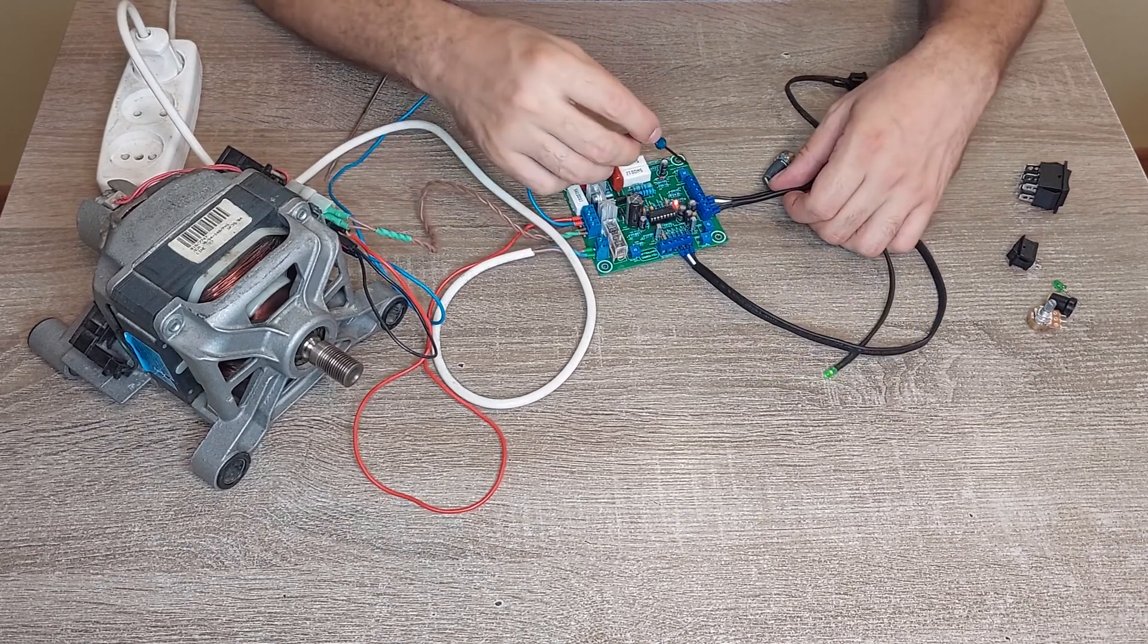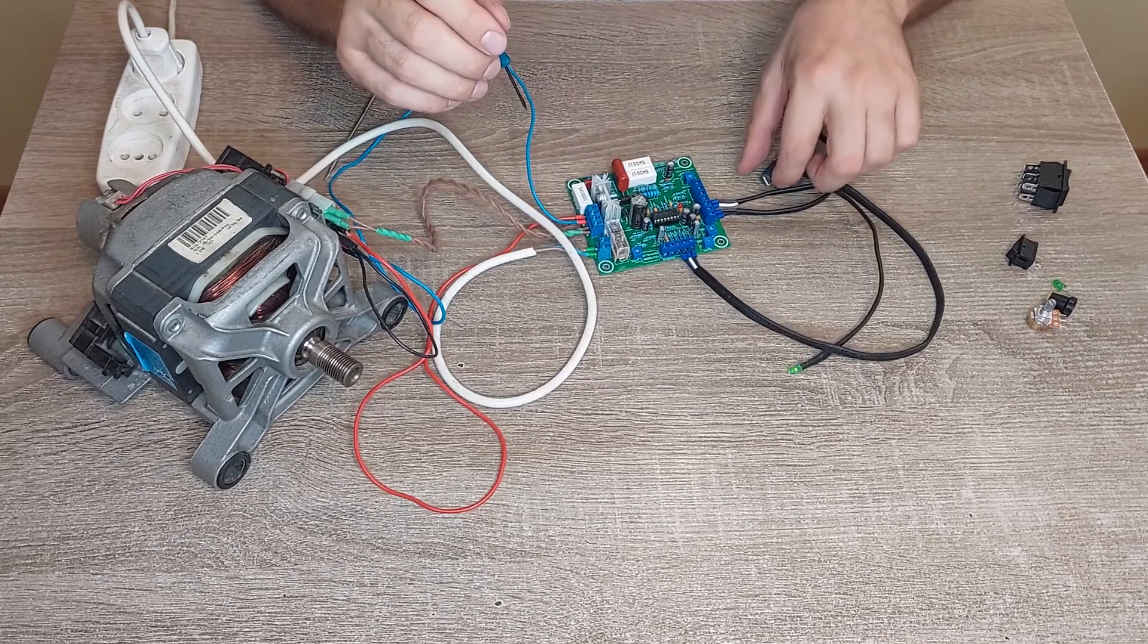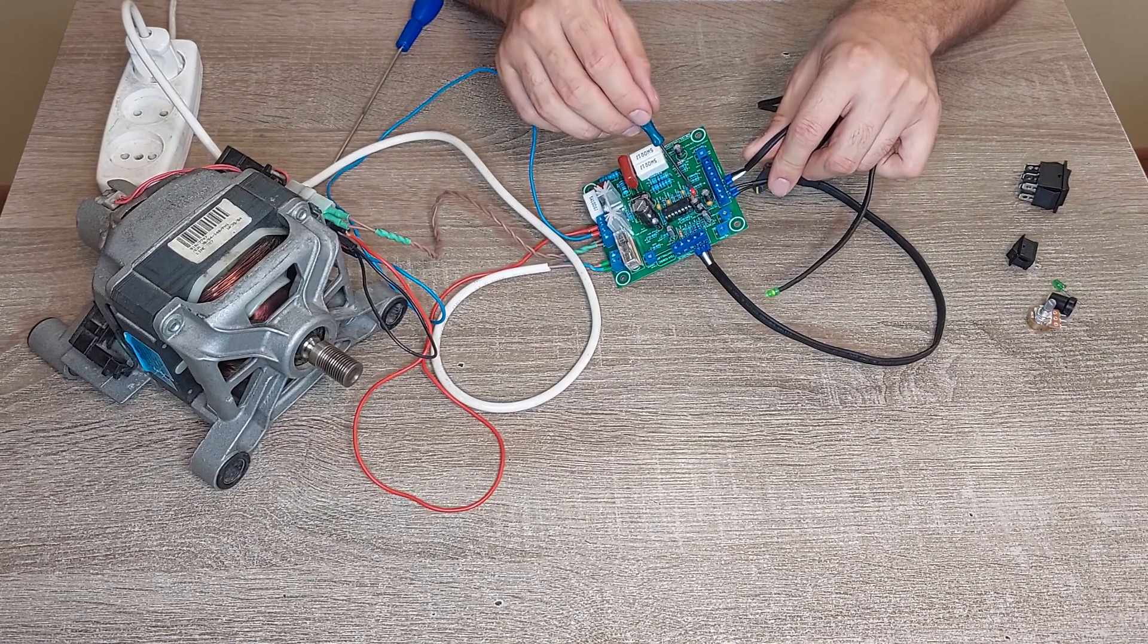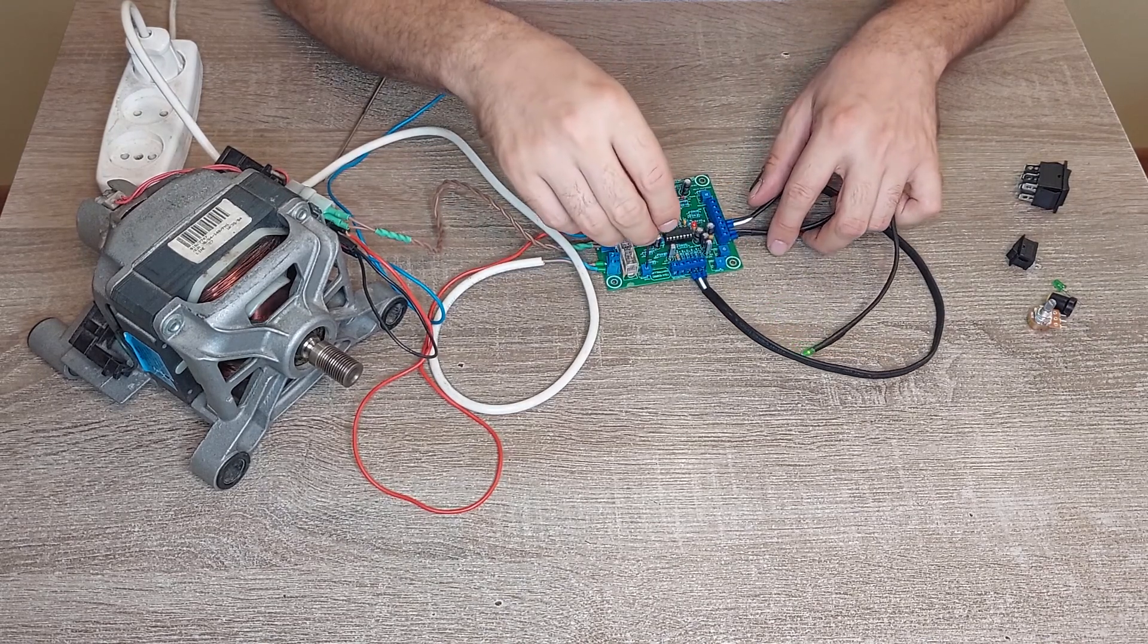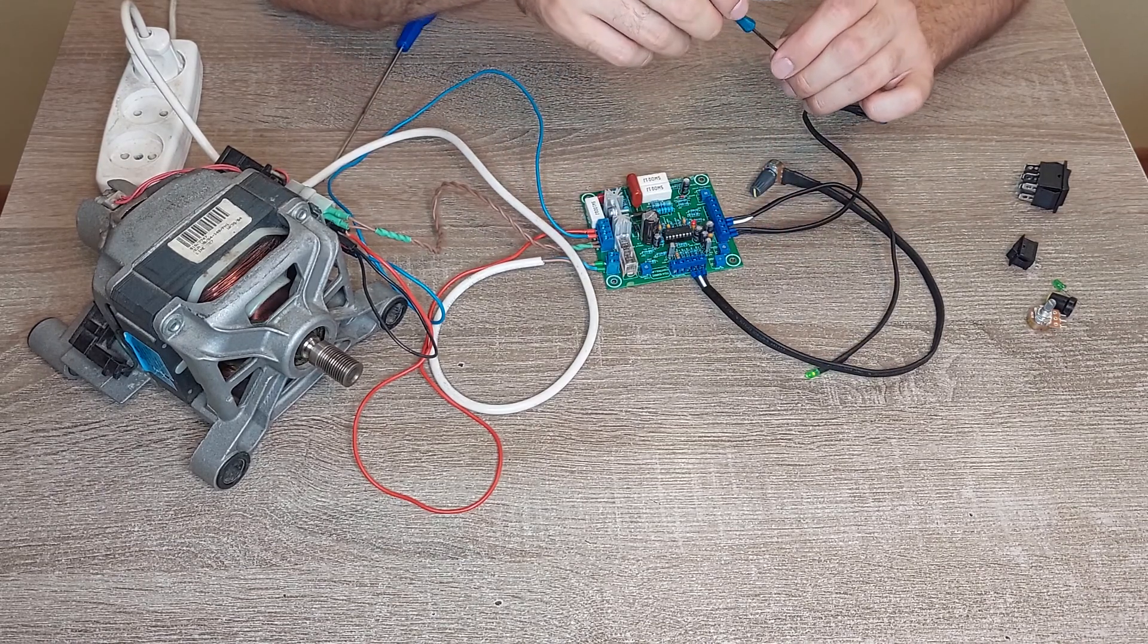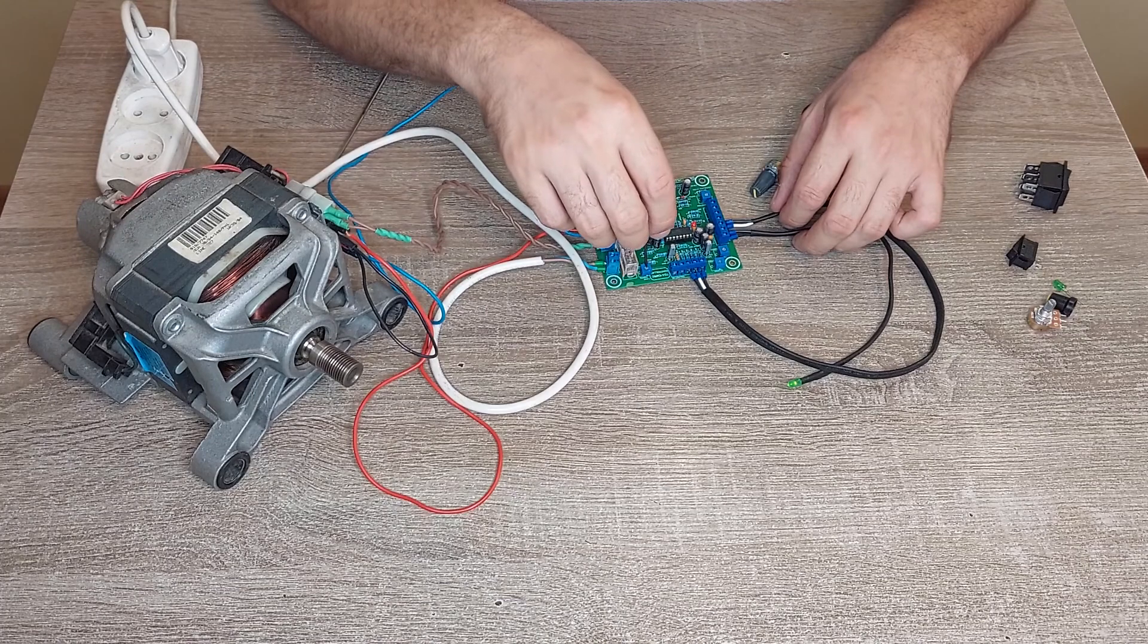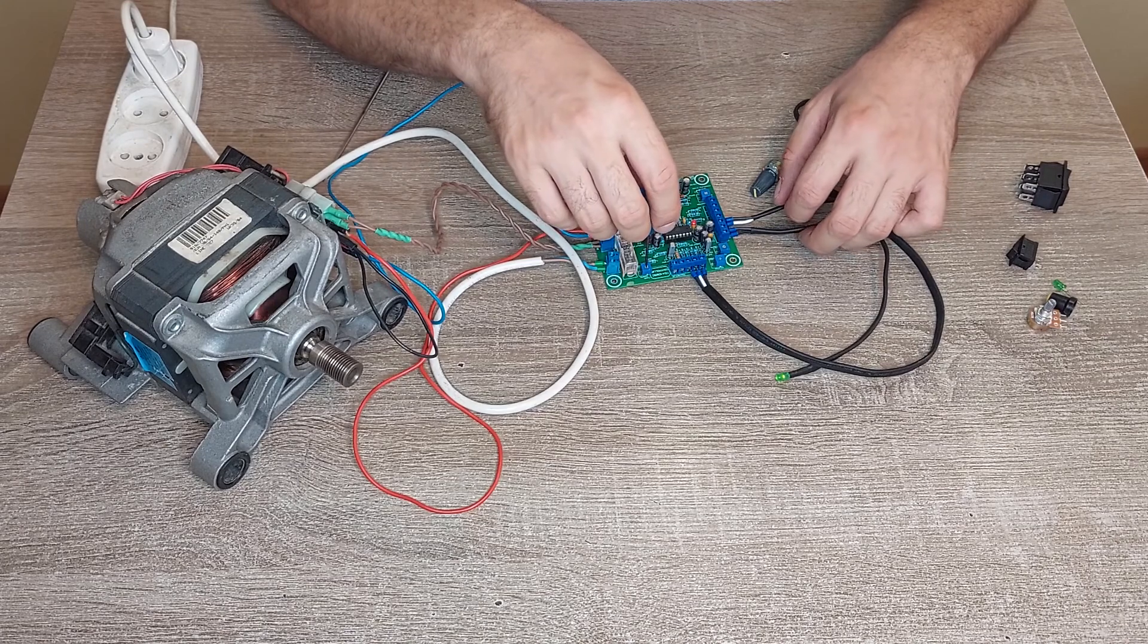Here are four turning resistors. First one: this is the Tacho config. Look—our LED indicator shows us that we receive the signal from the Tacho sensor on the motor. This Tacho config gives us the ability to control—if something goes wrong and we receive the signal but it's too low, we can turn this resistor and make it stronger.